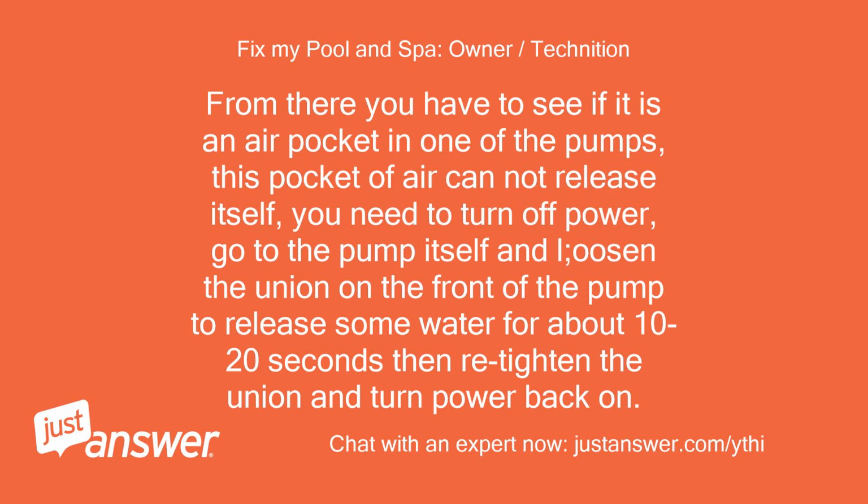From there you have to see if it is an air pocket in one of the pumps. This pocket of air cannot release itself. You need to turn off power, go to the pump itself and loosen the union on the front of the pump to release some water for about 10 to 20 seconds, then retighten the union and turn power back on.